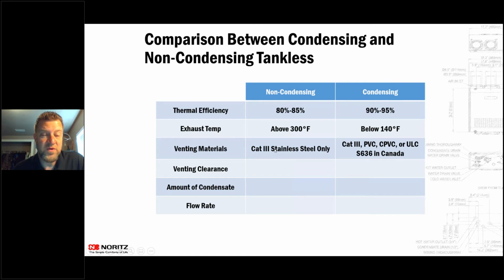So if you are going out to somebody's house, looking at an older non-condensing unit and you do want to change that out to condensing, but it is 4-inch stainless steel or 3-inch stainless steel going off that unit, we do manufacture adapters that will adapt to that stainless steel. It's stainless steel on one side and PVC on the other. So if you have somebody that has one of those older units, you can actually adapt it there, with the Cat 3 stainless steel, it won't corrode with the condensation going through it. You can actually bend that small piece coming off the top of the unit into that adapter in PVC, and then it still runs stainless steel the rest of the way out. So we do make those adapters, so you do not have to rip out all that old stainless steel and rerun it in PVC. You could just adapt it to that current stainless steel that is out there.